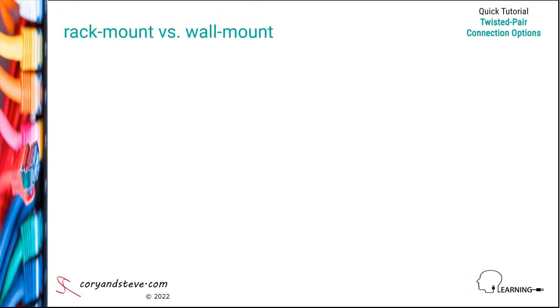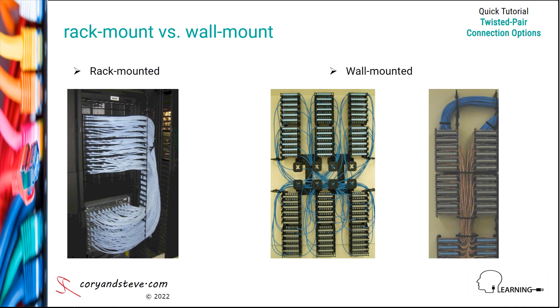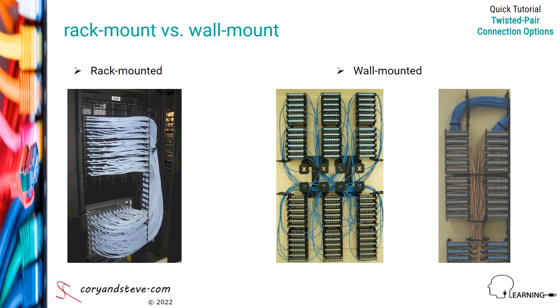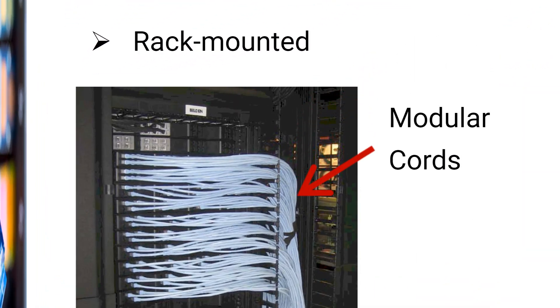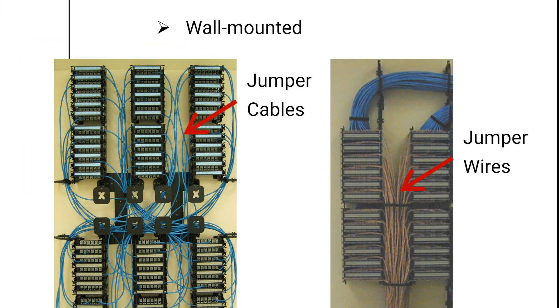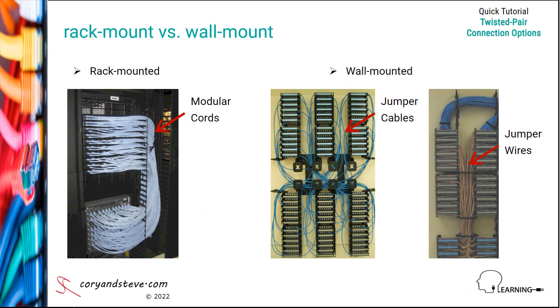We'll finish things off with a look at the mounting options for connectors at termination points. Connectors of all types can be rack mounted or wall mounted in telecom rooms, equipment rooms, or data center computer rooms. Rack mounting patch panels with modular cords is a common practice, but wall mounting with jumpers or patch cords can also be considered if space is at a premium or costs need to be minimized.